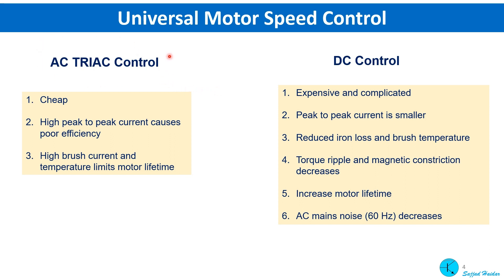For AC TRIAC control, it is cheap, but the high peak current causes poor efficiency, and high brush current and temperature limits the motor lifetime. On the other hand, the PWM control is a little more expensive and complicated, but the peak-to-peak current is smaller, iron loss and brush temperature are reduced, torque ripple and magnetic constriction decrease, and motor lifetime increases. Additionally, AC mains noise will decrease.